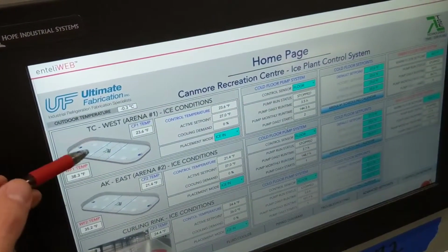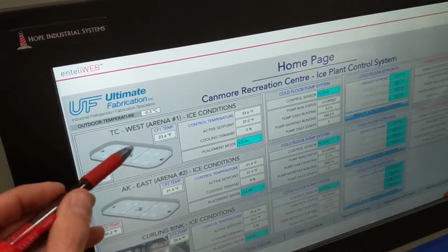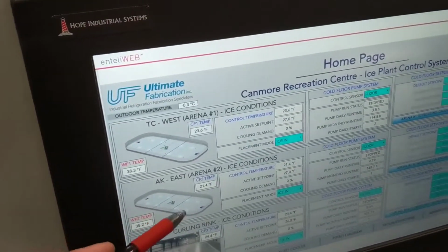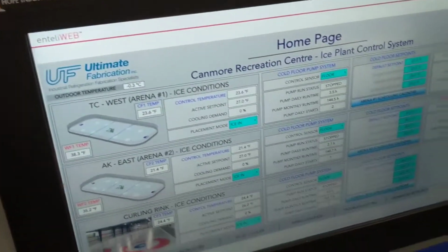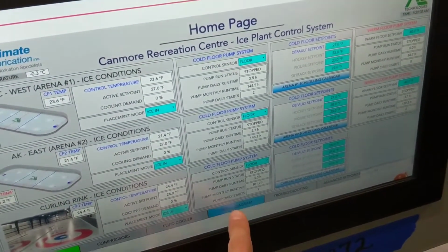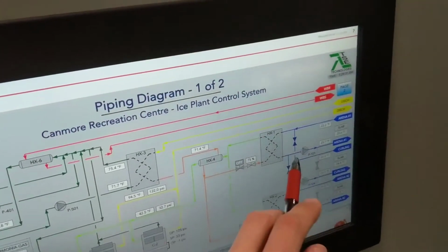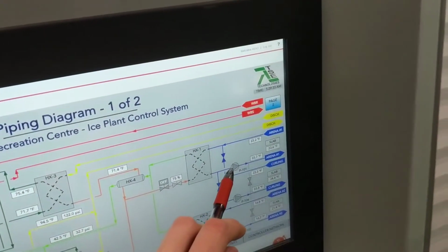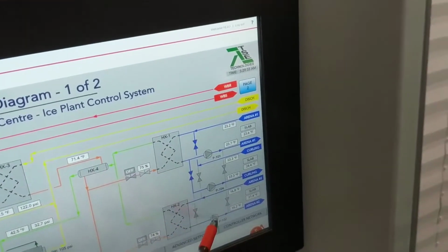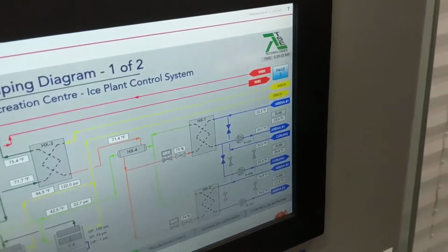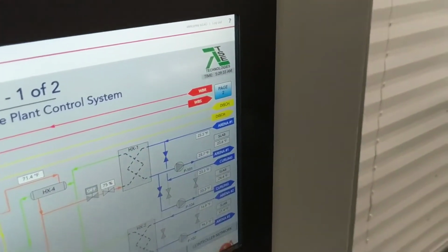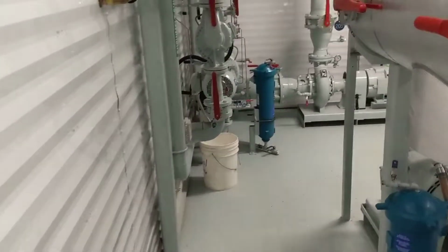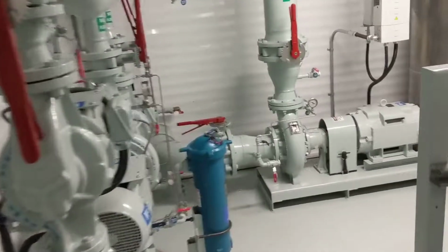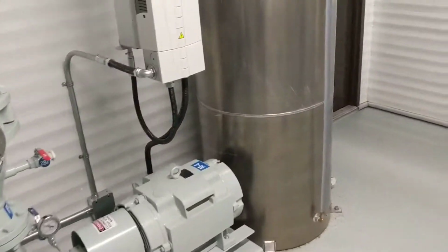So each of these floors has got a whole series of brine lines running through them. There's a supply header and a return header, and the pumps, which you can see on this piping diagram here. So these pumps, shown here, here, circulate the brine through the floors and through the heat exchangers. So as the brine circulates through the floor, it absorbs the heat that goes into the ice when you do a flood.